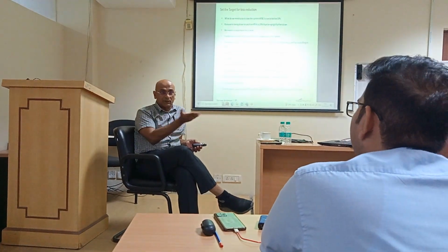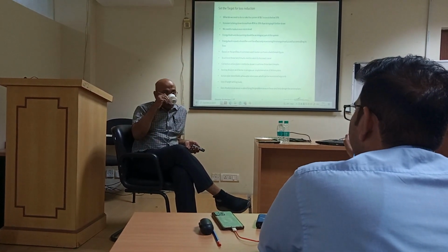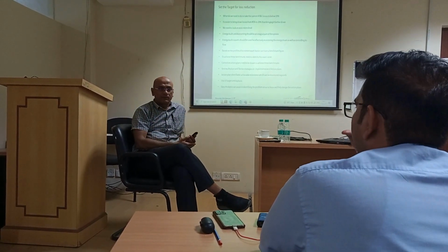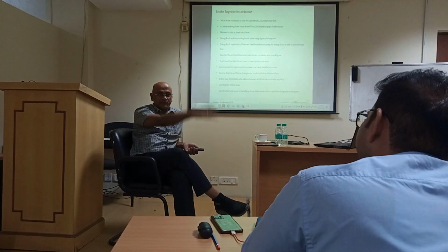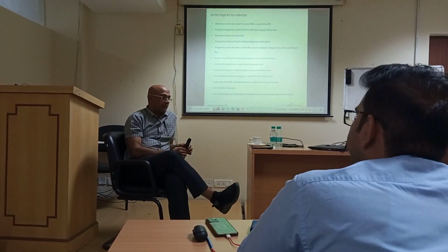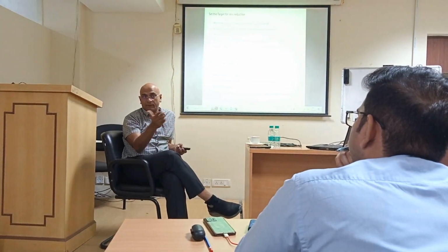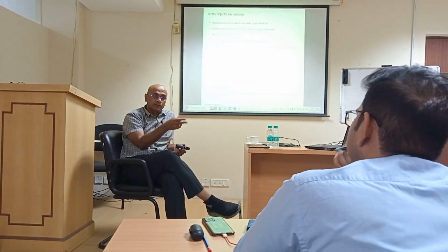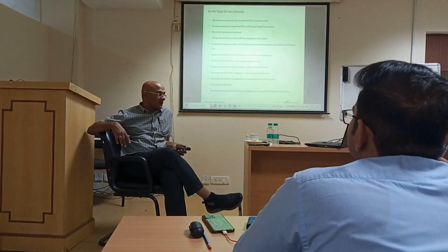I told you my experience about the result. I actually read that getting those AT&C losses down from a bigger figure to near about 20 is the easiest task, and the most stringent task is getting those 20 to single digit. It takes time. Even if you go for weight reduction, in the first few days you will reduce the weight, but when it becomes stagnant, it will not. Same thing here. If you see the loss reduction trajectory, from 53 to 25 they reached it in 2 to 3 years. Then from 25 to 8 they took 15 years.